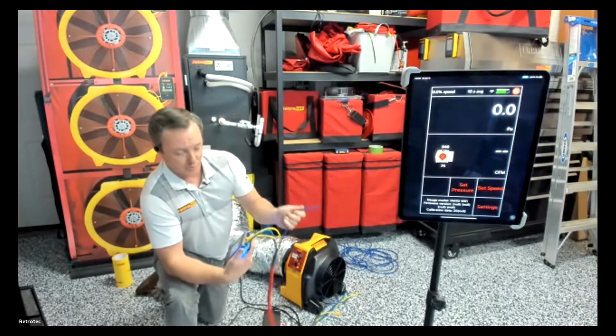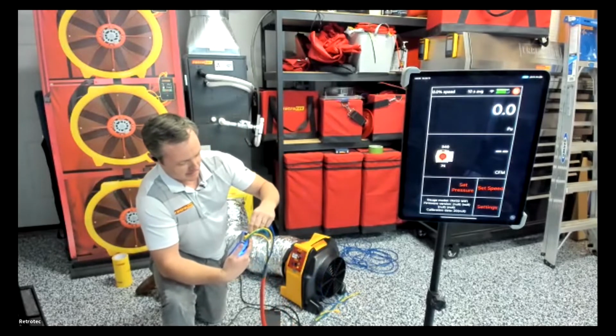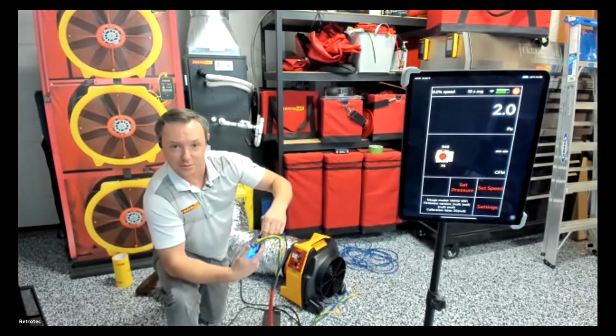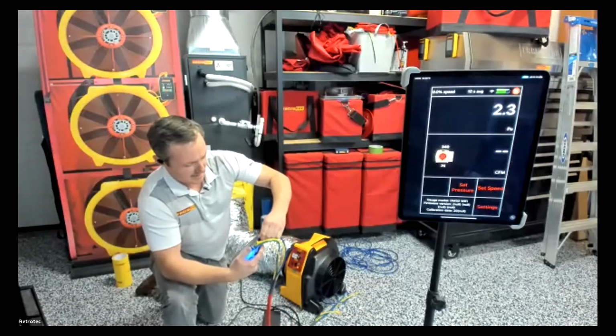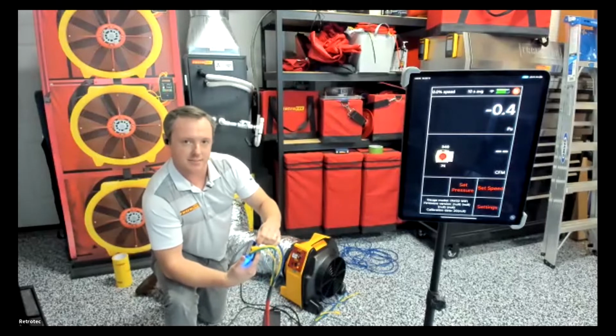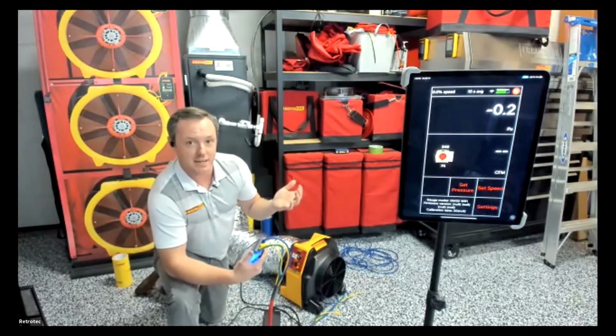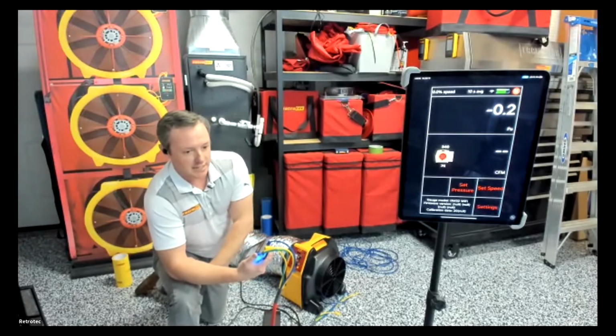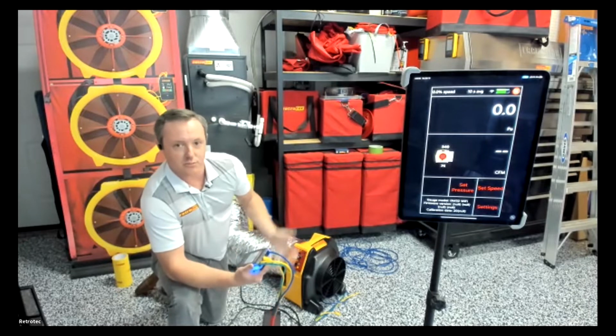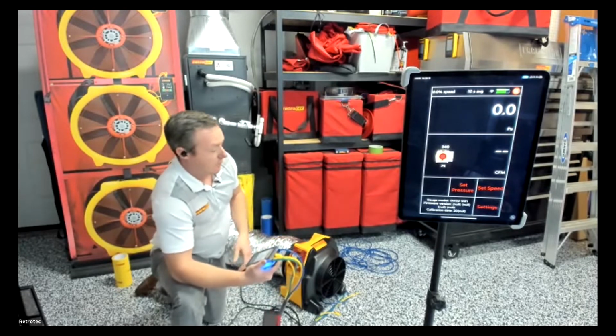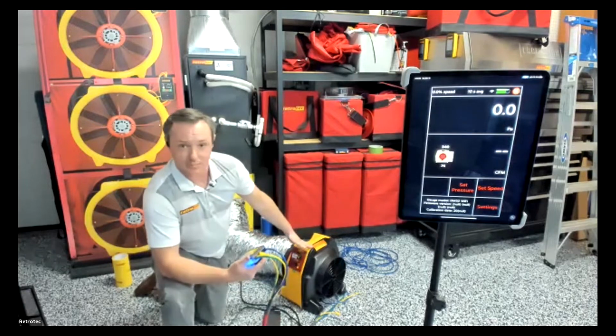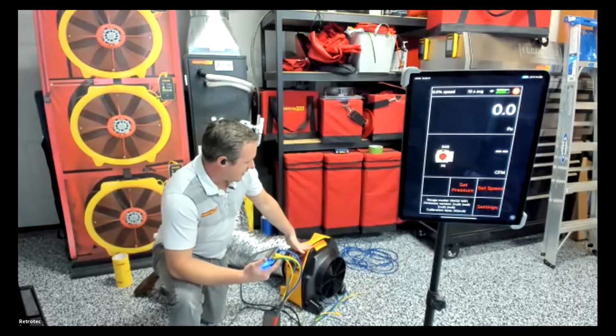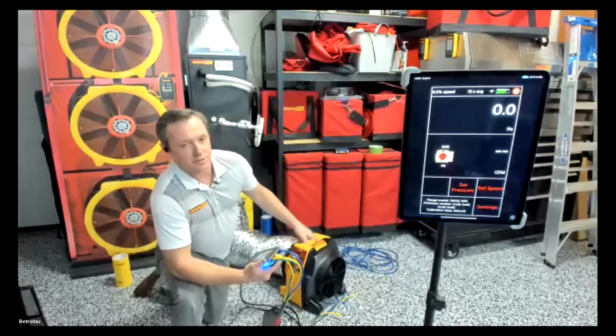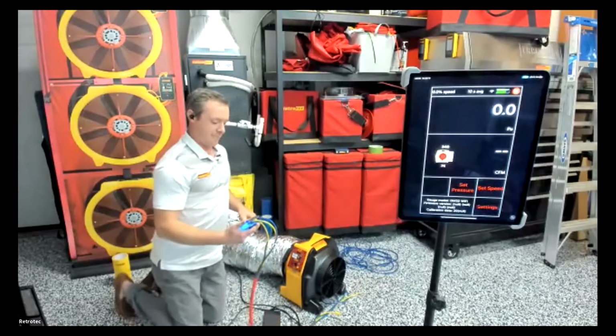And then we have this blue one that, you guessed it, goes to the blue port. This side is going to go to the duct system - we have to have something in there measuring the duct pressure. That way we know when we get to that 25 Pascal target, or negative 25 in this case, we're going to depressurize. That's how the manometer knows once we've gotten to that target pressure.